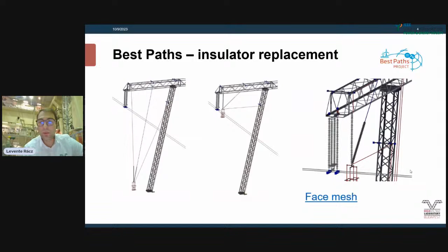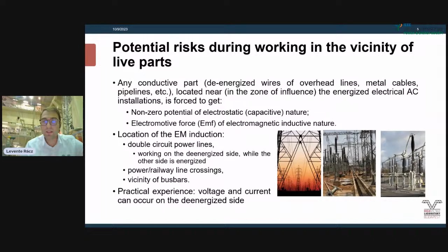If we move from live working to vicinity work, it's important to note that there could be problems also if you do not do live working, but work next to high voltage parts which are live. This situation can happen, as Balint mentioned, in double circuit power lines and also railway systems. Because of capacitive coupling, there could be induced voltage and induced current in these dead parts.